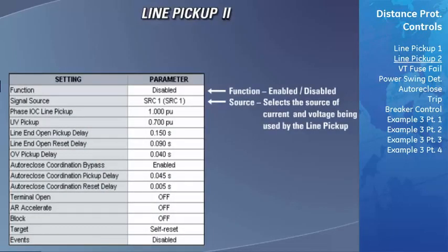We will now discuss all of the settings that need to be configured for the line pickup protection element to operate correctly. Before the line pickup feature can be used in the D60, it must be enabled in the function field. The source setting needs to be set to let the line pickup element know which currents and voltages to use to protect the transmission line.